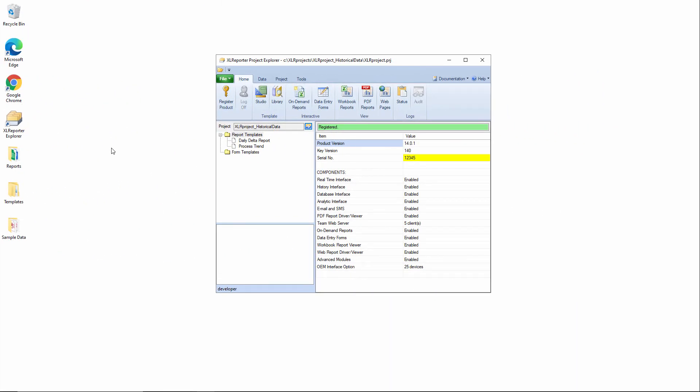The next scenario I'd like to cover is reporting for discrete events using a historical data source. Picture something like a batch-based process where a batch runs and every time the batch completes we add a row into a report that represents some summary calculations taken for the duration of that batch. So batch one runs from 12:30 to 1:15, at 1:15 when the batch ends, we use a live trigger in the PLC to capture some historian summaries taking place from 12:30 to 1:15 and add those summaries as a row value into the report.